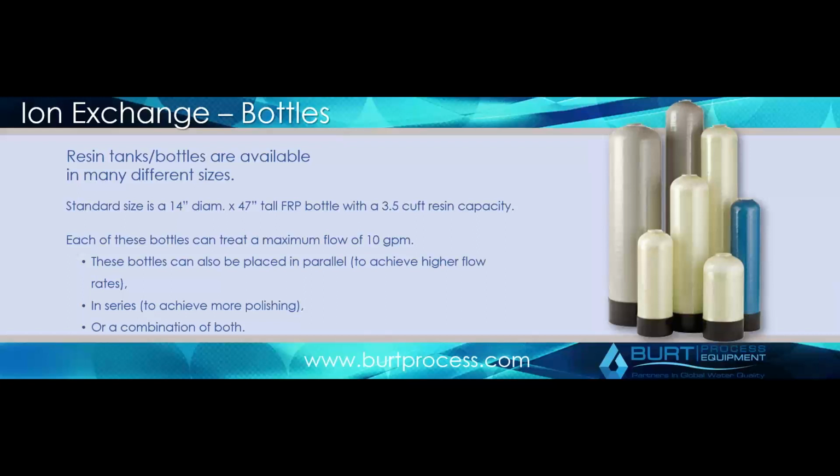It's going to essentially replace it with either a proton, which is an H+, or a hydroxyl, which is an OH-. The byproduct of the exchange then leads to the formation of just basic water. So I'm essentially pulling out these two charged particles, both anion and cation, and I'm going to end up with a neutral species of water in that case.